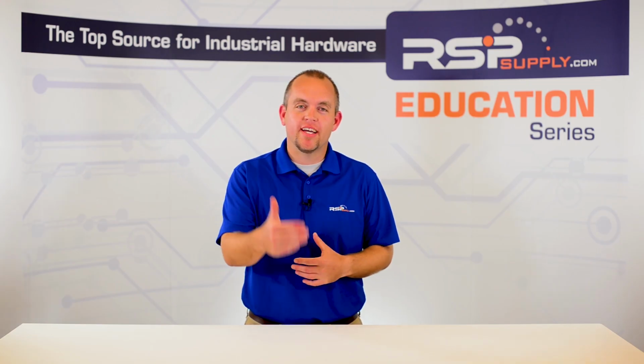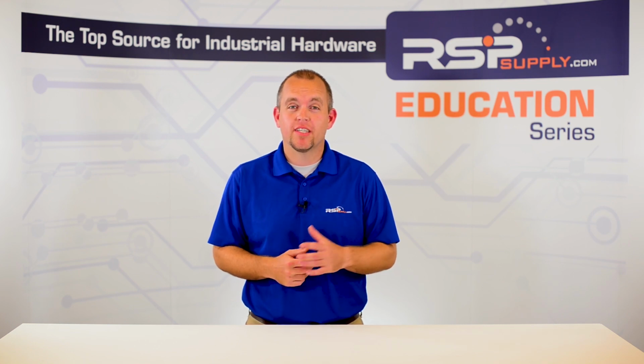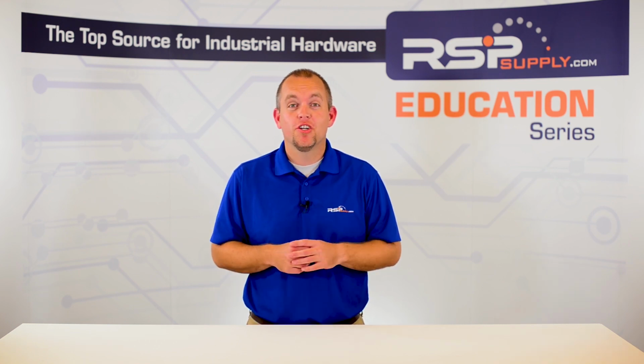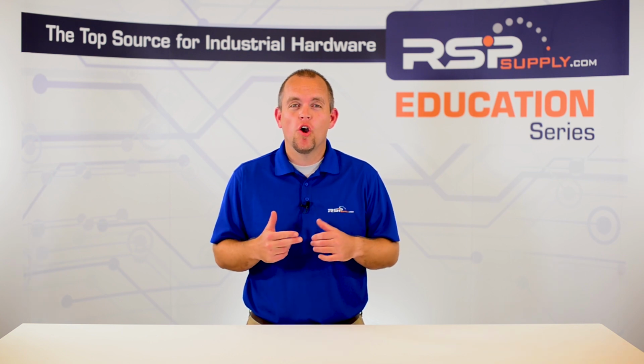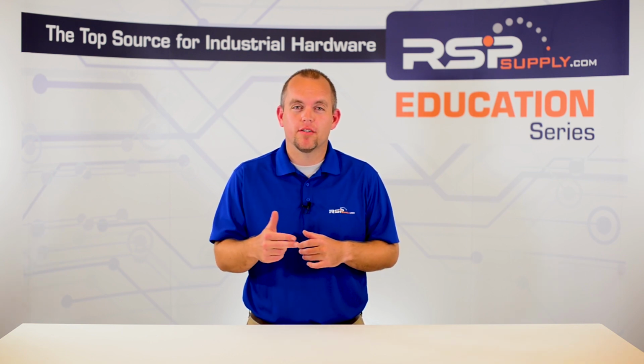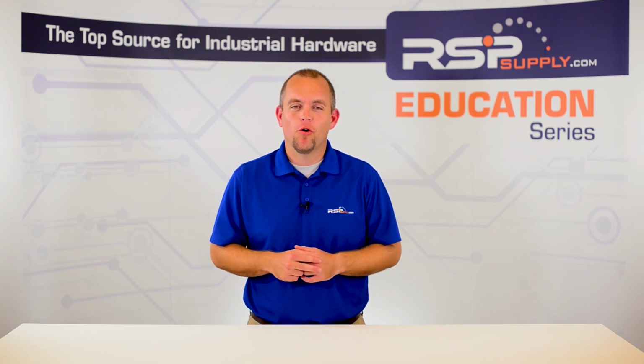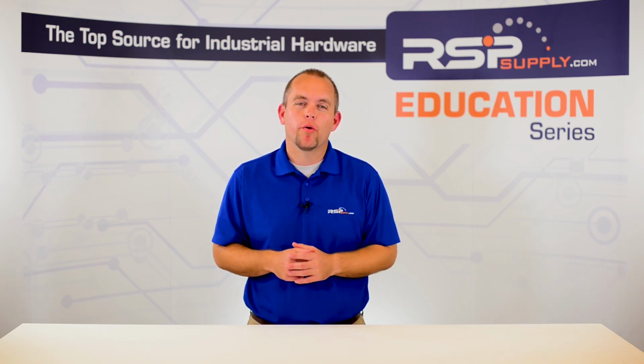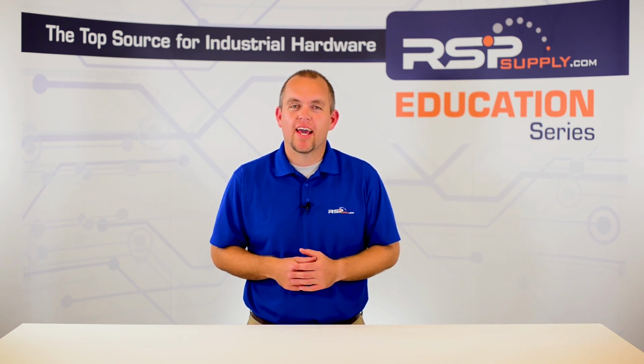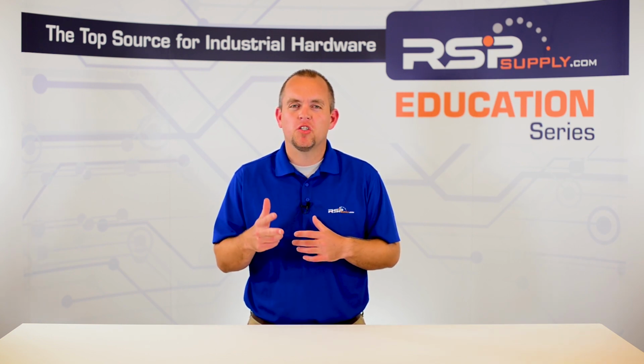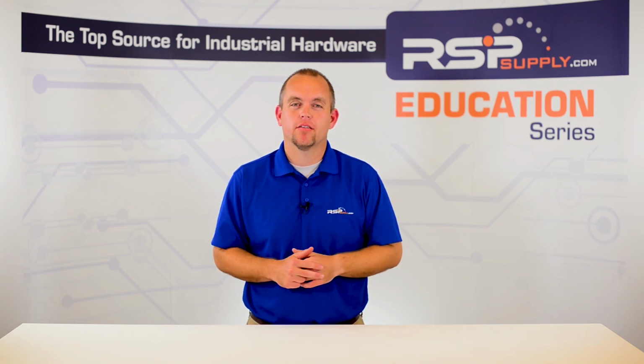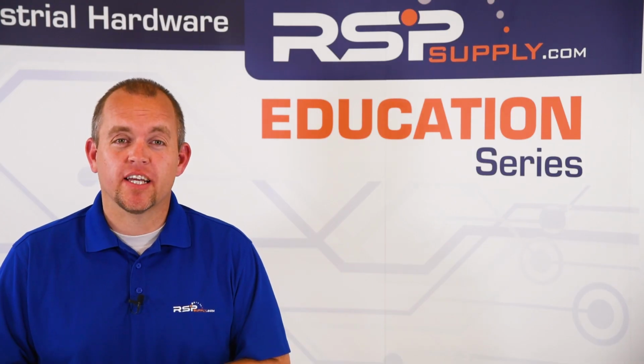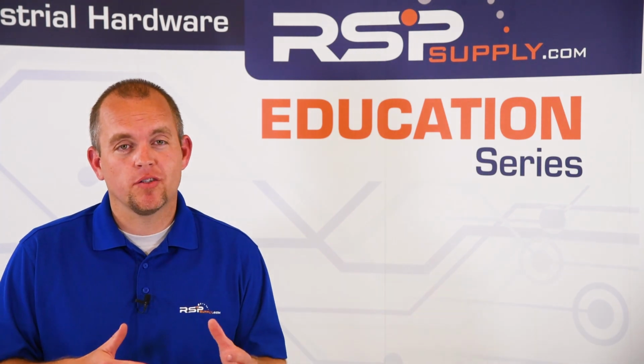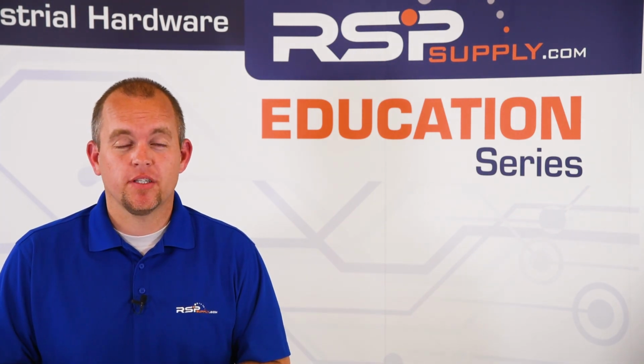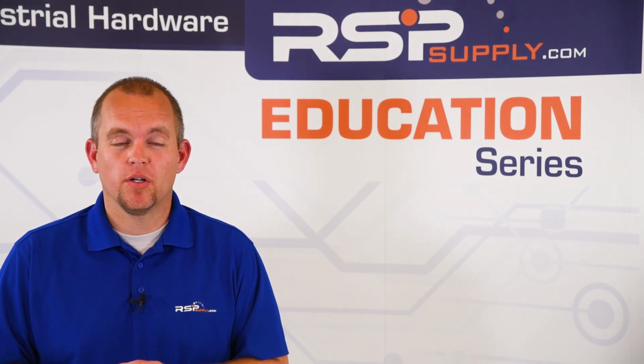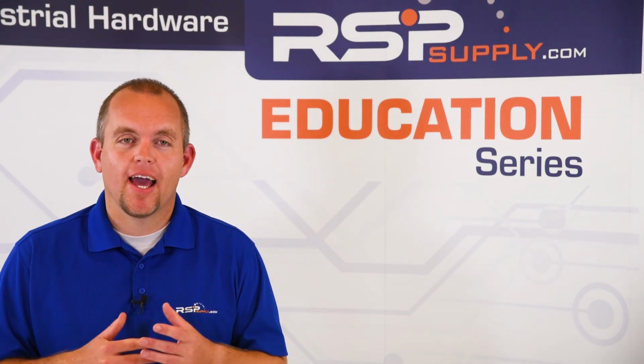Communication in a device can either be sent or received. Whether that data is sent or received is depending on the type of information. Do we need to monitor the status of something? If so, we need to receive an input about that information. Do we need to control something? If so, we need to send an output about what we want to occur. Receiving inputs and sending outputs are both things that can be accomplished by using both digital and analog signal types. So in this case, we start referencing signals as analog outputs, or AO, also analog inputs as AI, or digital inputs as DI, or digital outputs as DO.